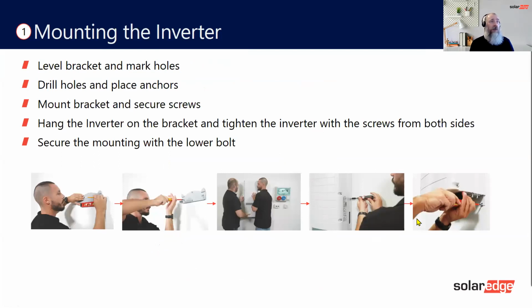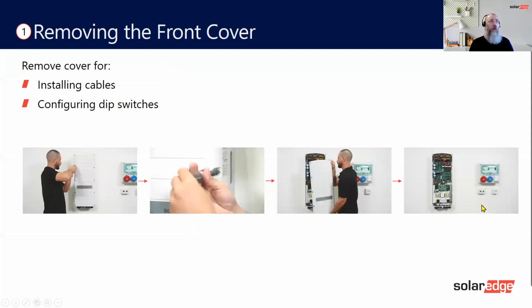It's the same bracket with all inverters. You install it exactly the same way. You then hook the inverter on the wall and you do the 2 screws up on the side. But with this particular one, you have a couple of bolts underneath. So you have a bracket just to secure underneath, similar to the DC safety unit. So if you're familiar with the DC safety unit that SolarEdge have on their inverters, it's exactly the same thing. Once you've done that, you can then remove the cover and you're left with this part here. So this is the inverter part, as I said, and then underneath is a DC to DC conversion.